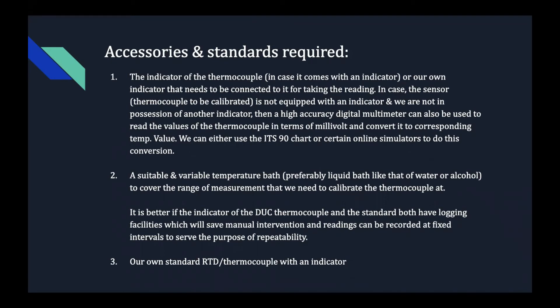In case the sensor thermocouple to be calibrated is not equipped with an indicator and we are not in possession of another indicator, then a high accuracy digital multimeter can also be used to read the values of the thermocouple in terms of millivolt and convert it to the corresponding temperature value.